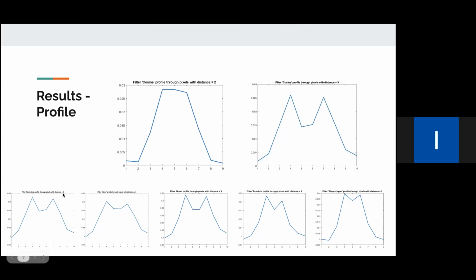Thinking back to our earlier slides, we can see that there's a connection between the reconstruction filter type and resolution. Both the Ram-Lak and Shepp-Logan have sharp edges, while the other filters for the most part have smoother shapes, which cause blurring.